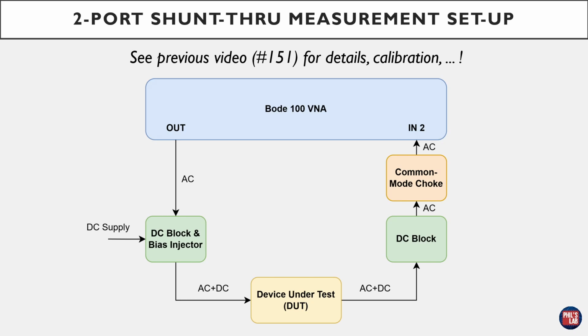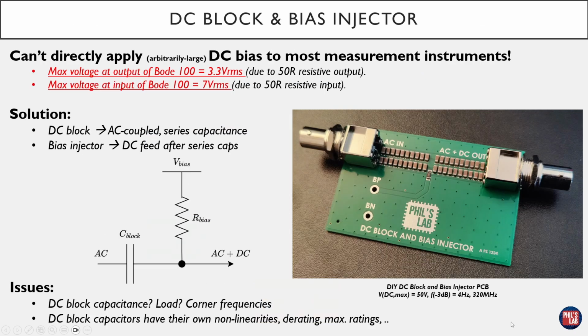We need to use DC blocks and bias injectors because typically we can't directly apply at least arbitrary large DC biases or voltages to most measurement instruments. For instance, the Bode 100 has a maximum voltage you can apply to its output of about 3.3 volts RMS because it has a 50 ohm series resistor to its output with a certain power rating. Similarly, for the inputs of the Bode 100, this is 7 volts RMS, again due to a 50 ohm resistive input setting for the 2-port shunt-through measurement.